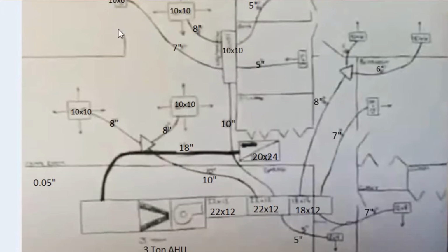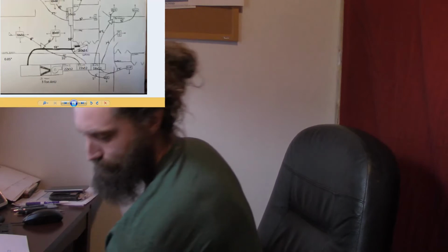But our ceiling diffusers themselves, okay, they have a pressure drop associated with them. If you're using a software, you may or may not have the ability to change the actual ceiling diffuser pressure drops, or they may have a generic catalog of pressure drops associated with specific registers, grills, and ceiling diffusers. Now, what I do is I've got books from Hart and Cooley. Okay, this is my local distributor. They have Hart and Cooley products, so in this book I can go through and determine what the pressure drop is of any floor register, sidewall register, grill, ceiling diffuser, whatever. It's all in here. There's a commercial version of this book and a residential version of that book.